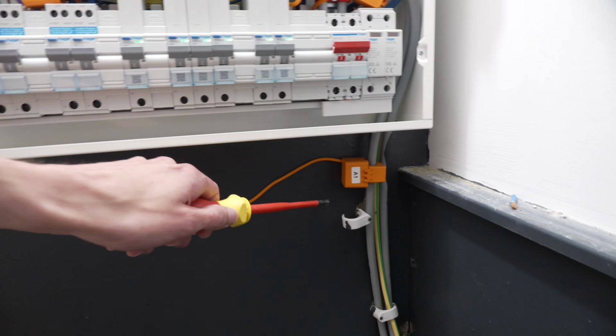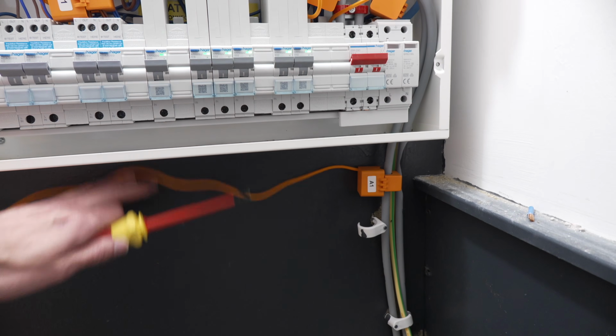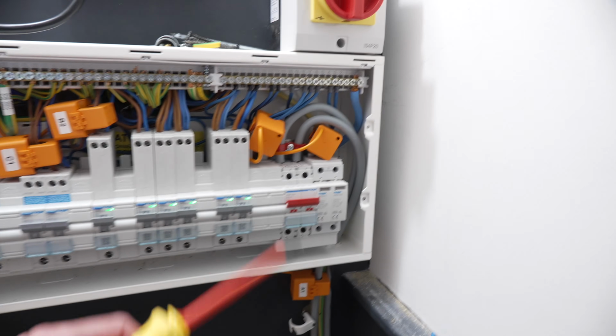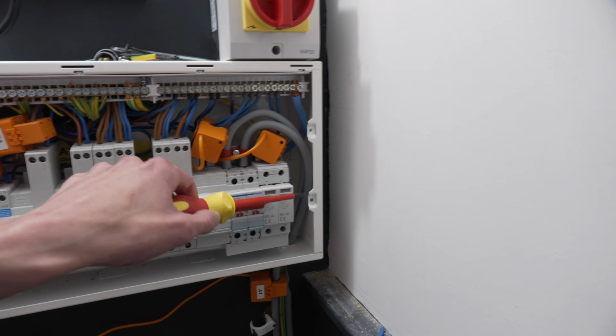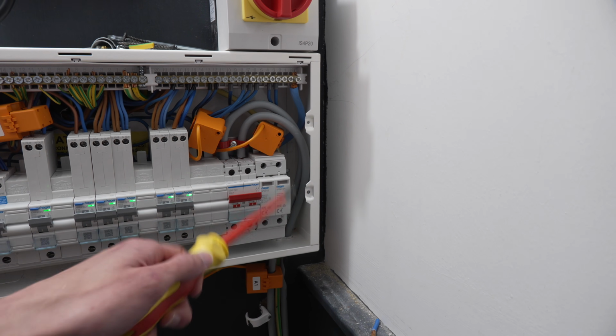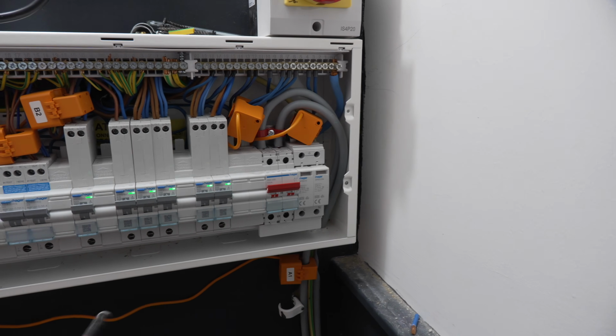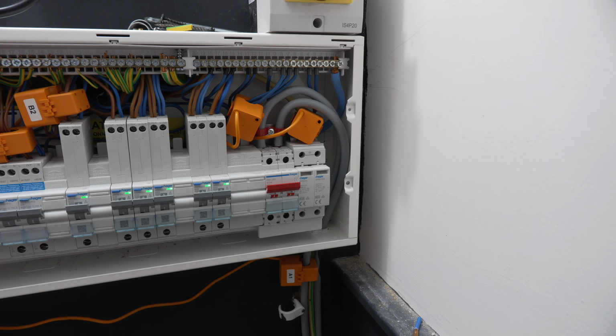What I ended up doing was, instead of installing it inside the consumer unit here, I brought the cable out the stuffing gland at the bottom and connected it onto the meter tails externally, and I'll just clip this up and out of the way. The reason I did that is because, as you can see, the meter tails come in here and curve round. There's already a CT in this area, and these meter tails, they're not nice flex tails, they're just standard tails, so they're very, very thick and very stiff.